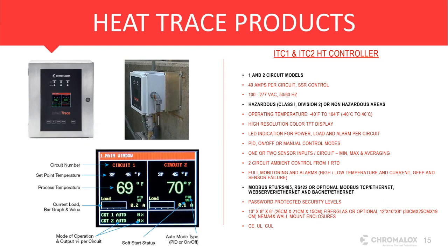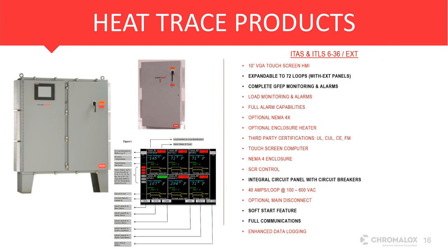If you need more than one or two runs, that's when you get into our larger panels, which would be our ITLS and ITAS. AS is for ambient sensing, LS is for line sensing. It's important to remember that these come in 6 circuit buckets, so you can get up to 72 loops or circuits in one panel. And then we have extension panels to go with that. The HMI display mirrors the smaller one, and it has all your controls. They're easy mapping sensors, and it's a great product that makes your design, your install, your takeoff, your project very easy to do with our design guides and everything available.